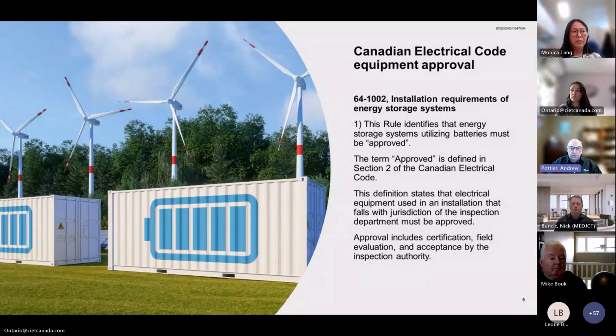This new rule, 64-1002, speaks about installation requirements for energy storage systems and specifically says that an energy storage system has to be approved. An energy storage system utilizing batteries shall comply with Rule 2-024, which provides direction to code users, installers, and designers that an energy storage system must follow certain criteria to become approved. This may mean full certification, where the system is certified off-site and then shows up either reassembled or self-contained in a container, or it's built in the field and still required to be approved.